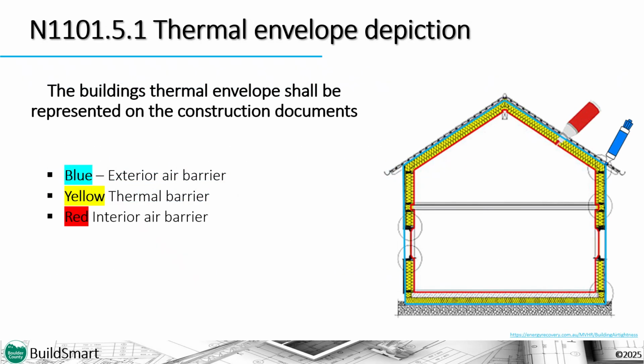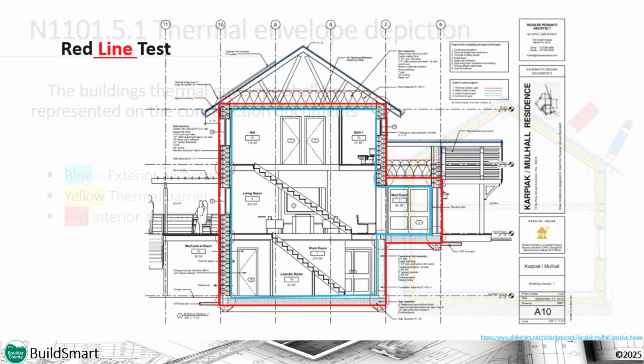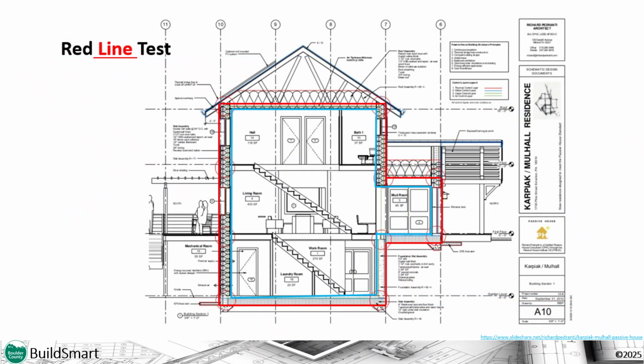Remember that when a section is called out in the mandatory requirements table, all subsections are also requirements. In this case, the design team is required to depict the building thermal envelope on the construction documents. This depiction is often called the red line test and is generally done on one or more sectional drawings.